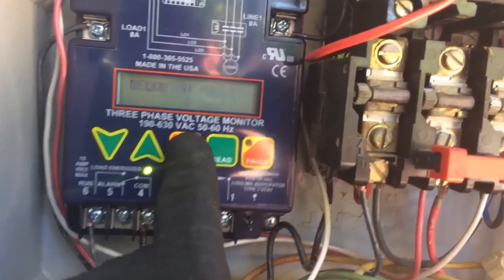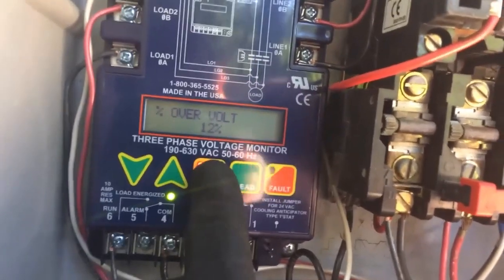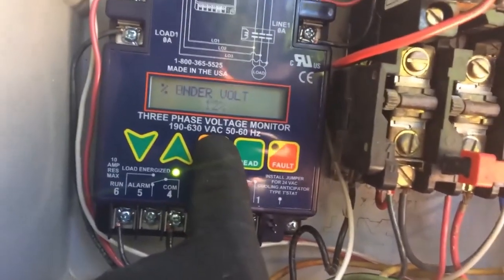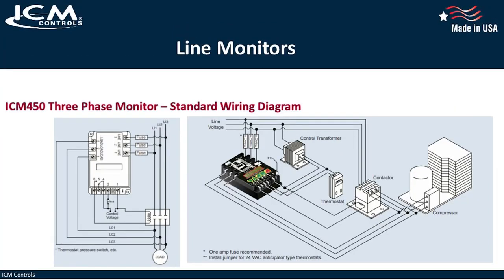It also lets you set the imbalance percent at which the unit will take your equipment offline to help avoid nuisance trips. The ICM 450 is wired in parallel with your system. This is important to note, as it is not controlling the contactor. It is merely monitoring the power that is coming into your system. The ICM 450 monitors the line side, and it also checks the load side of the contactor at startup.